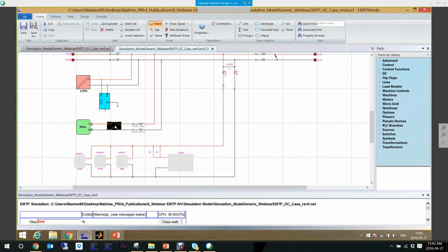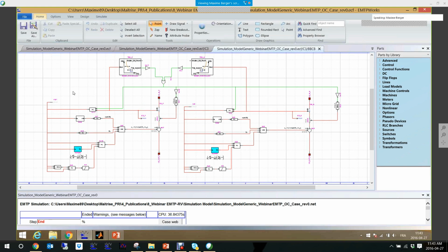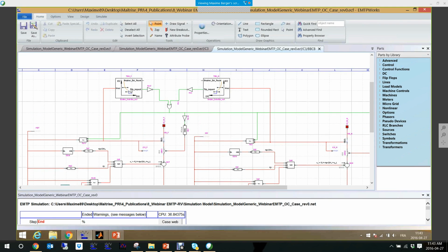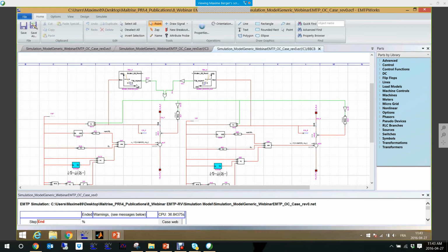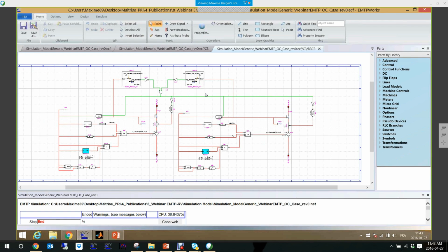And here, inside the circuit breaker, we have our arc model, which is here, and it receives a trip signal coming from here, which is the detection block that recreates the thermomagnetic trip unit of the circuit breaker. And for a two-pole circuit breaker, we need to model these two poles using two voltage sources that recreate the arc voltage function.